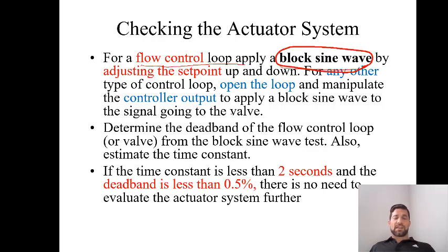By using progressively increased step changes to your set point, you can see at which point the valve actuator actually responds to the changes. Because valves are going to have a deadband and a time constant associated with them, we can determine those by doing this type of block sine wave.